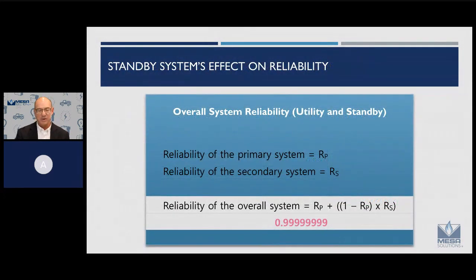So when you put that all together with the reliability of the utility system in our example, you really have a tremendous amount of reliability. I think that's 8 nines. You probably don't need that much. So if it calculates out that way, you might say, well, I don't need N+1 for my standby system, I can get by with just N.